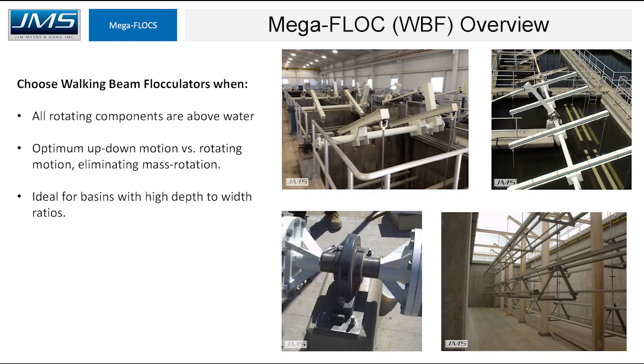You might want to choose walking beam flocculators when all rotating components need to be above the water. The optimum up-and-down motion prevents mass rotation and creates the highest quality floc particle possible. They are ideal for basins with high depth-to-width ratios.